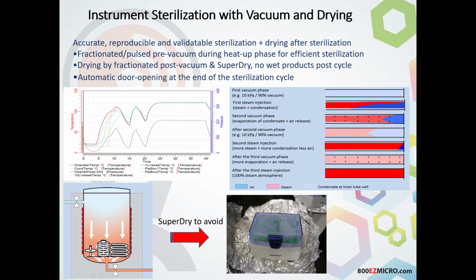And so what we would do when we start a sterilization cycle is we will begin a pre-vacuum cycle. So it will vacuum air out of the system, and then we're going to do a steam inlet. So we'll do 3 of those, and the diagram there shows you how we are able to achieve complete steam penetration even through hollow items after those 3 pre-vacuum cycles and steam pulses. So once we've achieved the 3rd pre-vacuum and steam pulse, then we're going to have a complete steam environment inside of the unit.